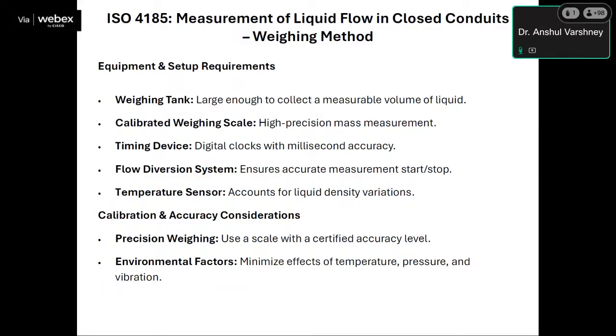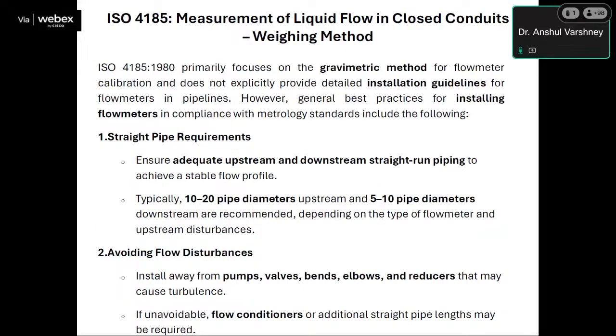So earlier I said a precision weighing system is required, which uses a scale with a certified accuracy level. Environmental factors: minimize effects of temperature, pressure, and vibration. So basically, ISO 4185/1980 primarily focuses on the gravimetric method for flow meter calibration and does not explicitly provide detailed installation guidelines for flow meters in pipelines.